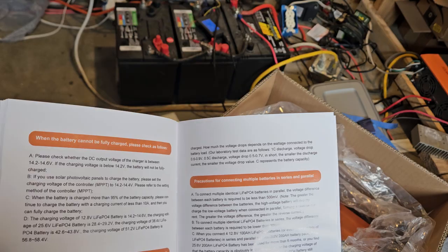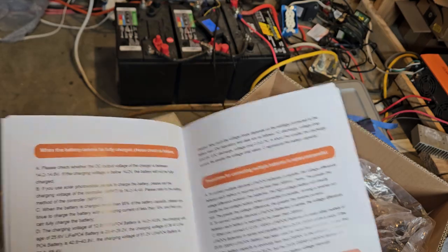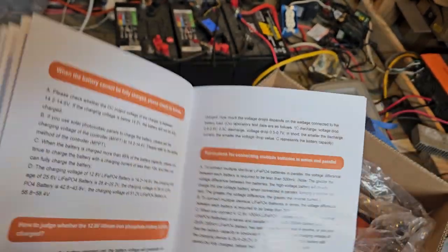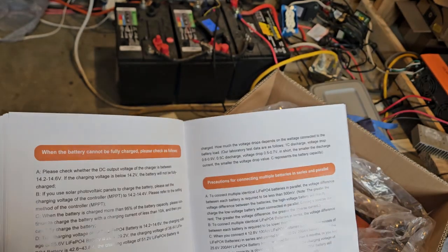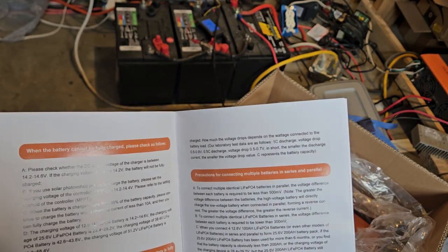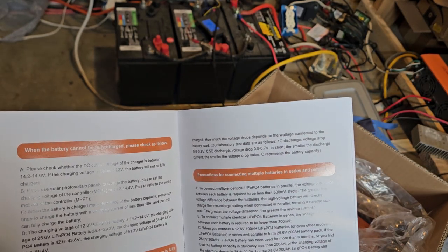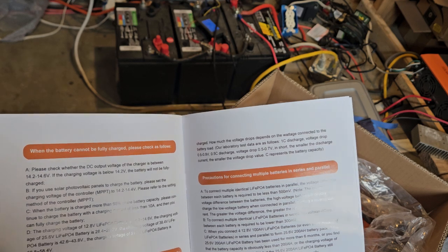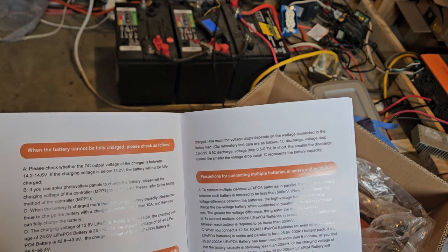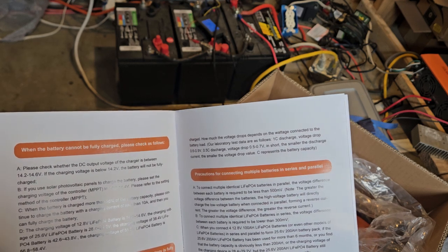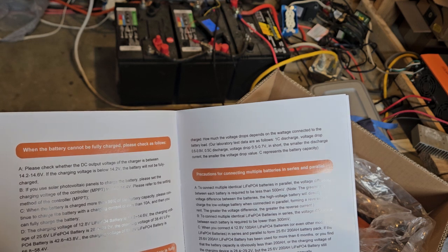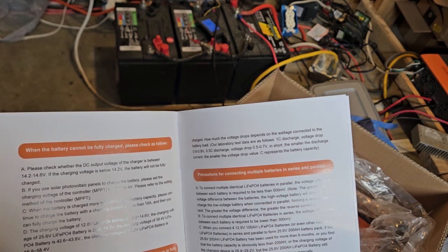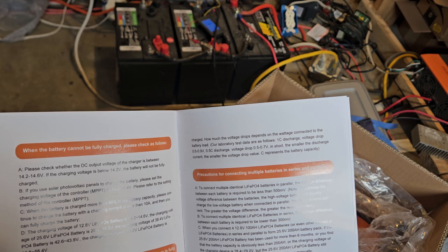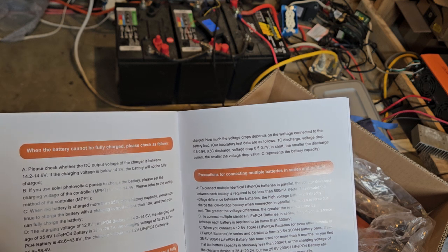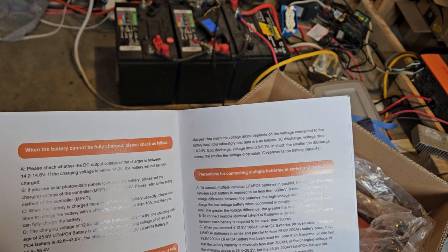Okay, so I want to go over this before I get all excited and hook up batteries, just for my own purpose too, just to see if they have anything interesting. To connect identical batteries in parallel, the voltage difference must be less than 500 millivolts. The greater the voltage difference between the batteries, the high voltage battery will directly charge the low voltage battery when connected in parallel, forming a reverse current. The greater the voltage difference, the greater the reverse current.